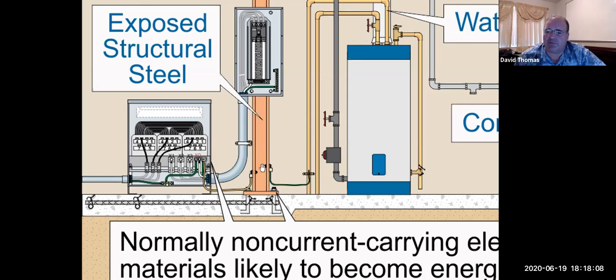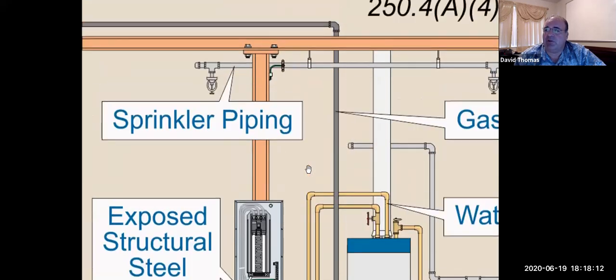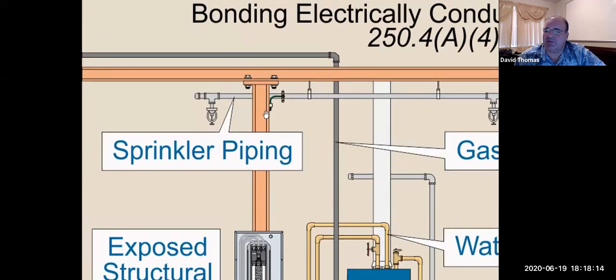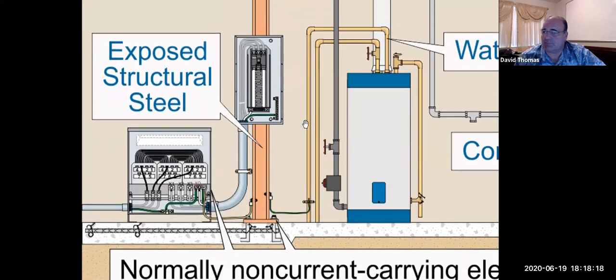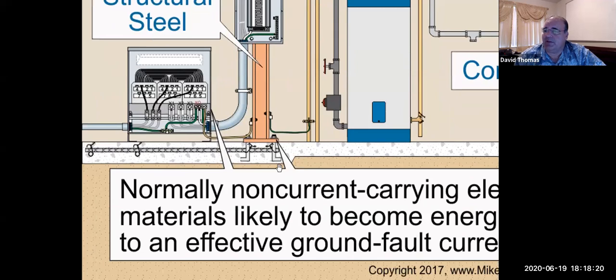So here we went from the building steel to the water pipe. We can actually go from the building steel to the sprinkler pipe, and so on, okay? And then that can be tied into the electrical system right through that main bonding jumper right here, and that ties into the ground and the neutral eventually, okay?